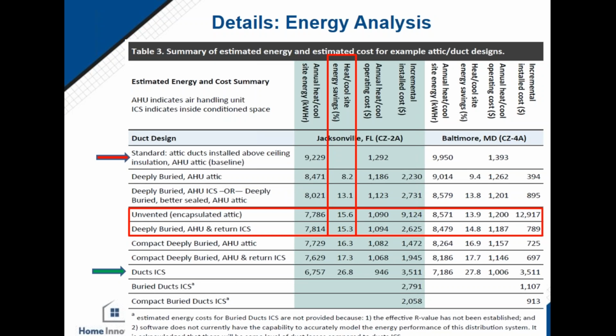Michael made a suggestion of building a box of rigid foam insulation and encapsulating the air handler in that so it can be removed for service. We had another question: is there an energy penalty for the air handling unit being exposed in the attic? I don't know if there's such an energy penalty or not. Well, I think the software takes into account the location of the air handler. The losses are primarily the duct, but certainly the air handler poses a potential loss for sure. So I rely on the software to recognize whether the air handler is in inside conditioned space or up in the attic.